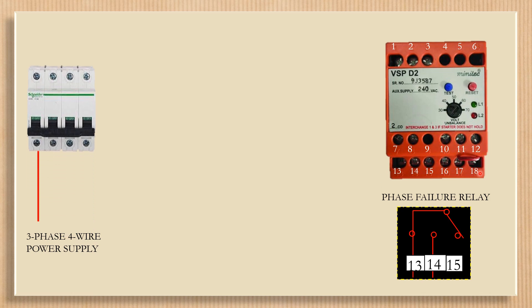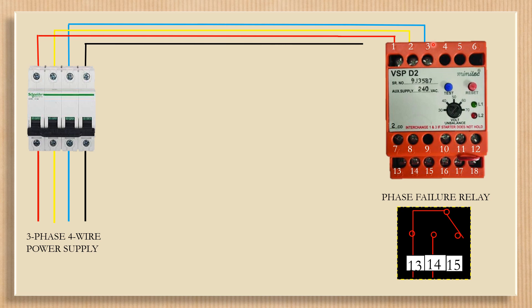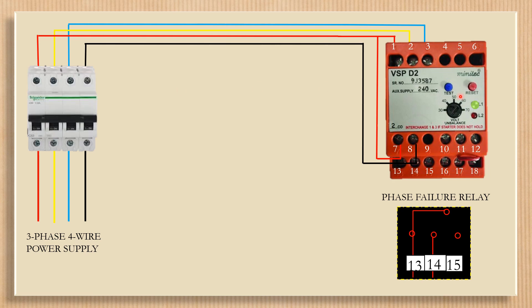Contact one to three are connected with the three-phase power supply. Contact seven and eight are connected with auxiliary power. When the three-phase MCB is switched on, the instrument gets power. The green lamp will illuminate and contacts thirteen and fourteen will be made.